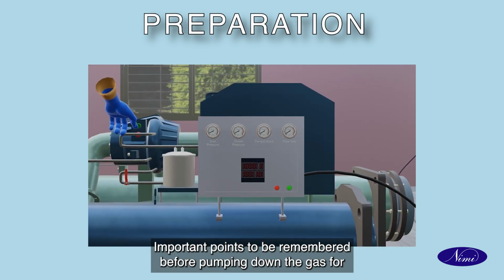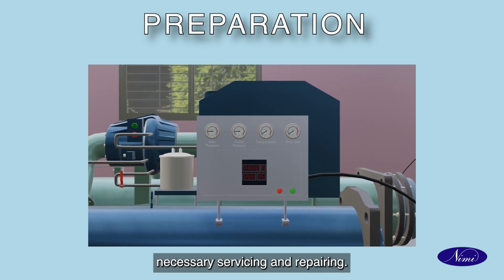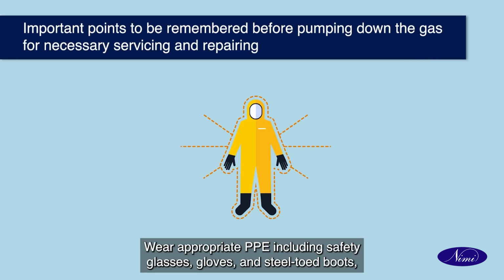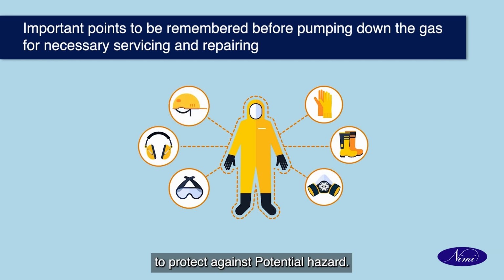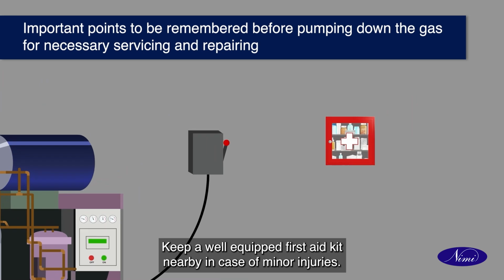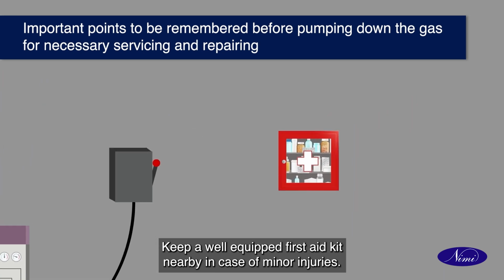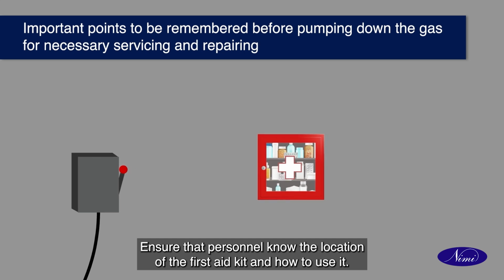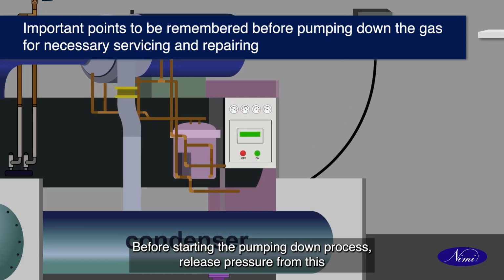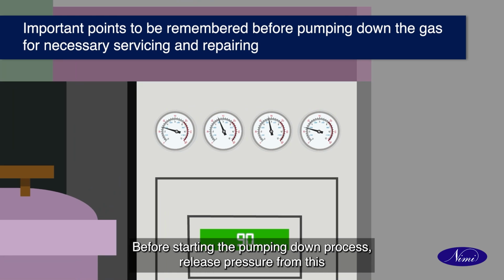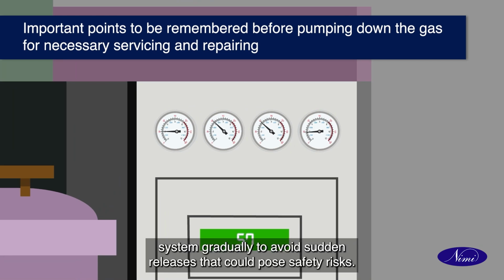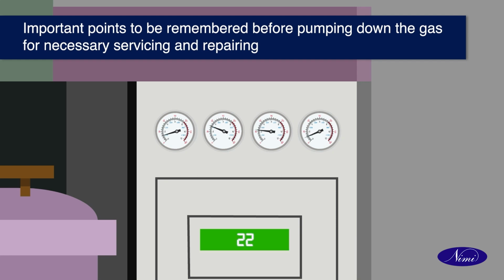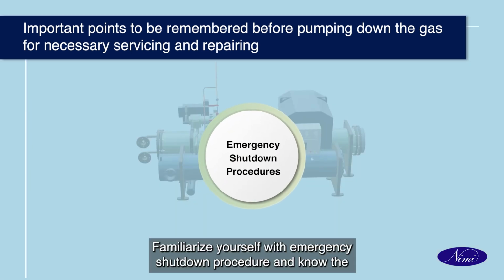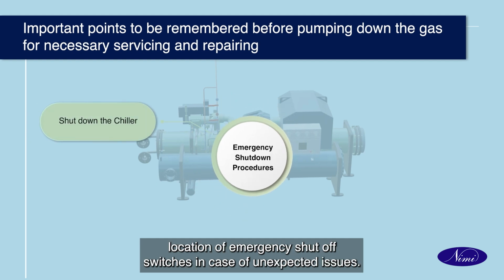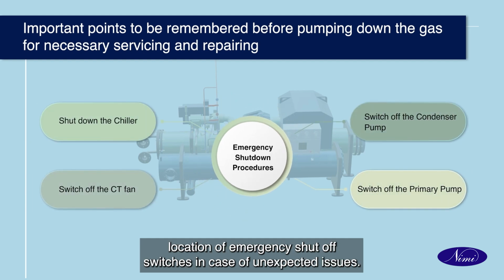Important points to be remembered before pumping down the gas for necessary servicing and repairing. Wear appropriate PPE including safety glasses, gloves and steel-toed boots to protect against potential hazards. Keep a well-equipped first aid kit nearby in case of minor injuries. Ensure that personnel know the location of the first aid kit and how to use it. Before starting the pumping down process, release pressure from the system gradually to avoid sudden releases that could pose safety risks. Familiarize yourself with the emergency shutdown procedure and know the location of emergency shut-off switches in case of unexpected issues.